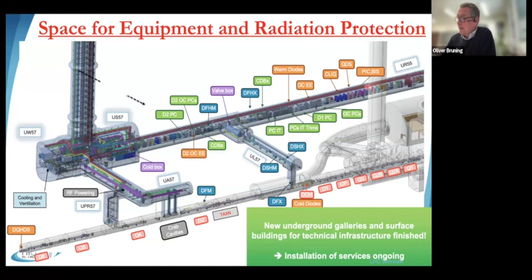And then one of the resulting challenges is that we have to connect the power converters from these new galleries that we built to the existing tunnel. And that means we have to carry currents of 100 kiloamps about 100 meters from the new galleries to the existing tunnels. A big challenge. If you do this with water-cooled copper cables, you would have to face immense cooling power and electricity bills. And we adopted a new approach here.